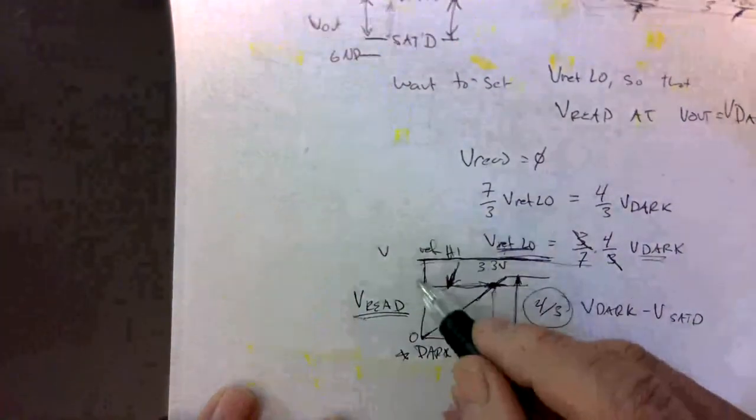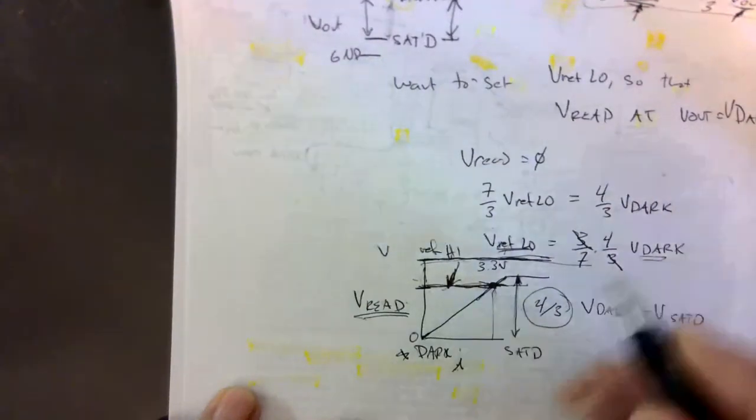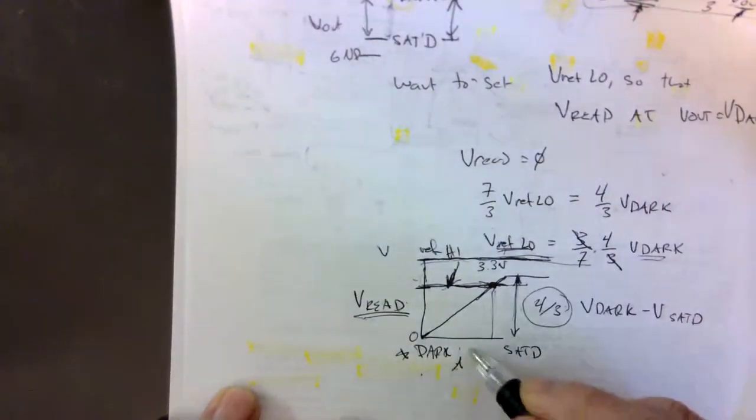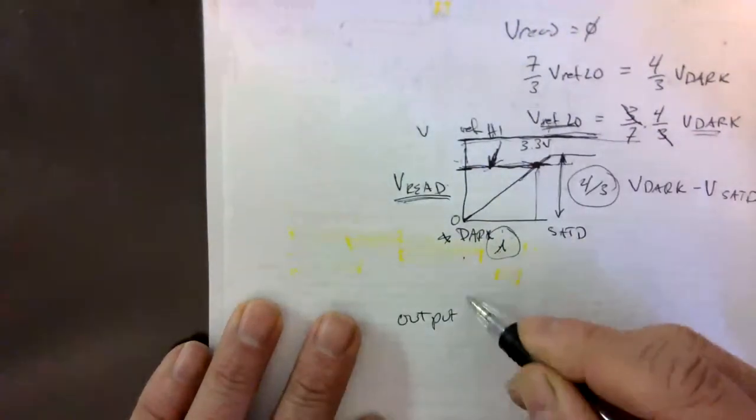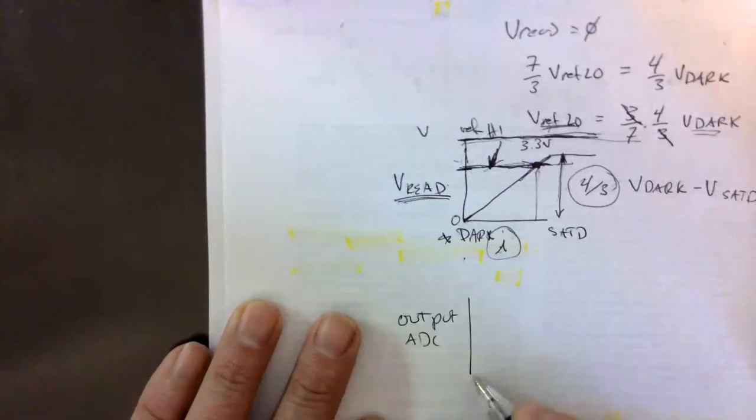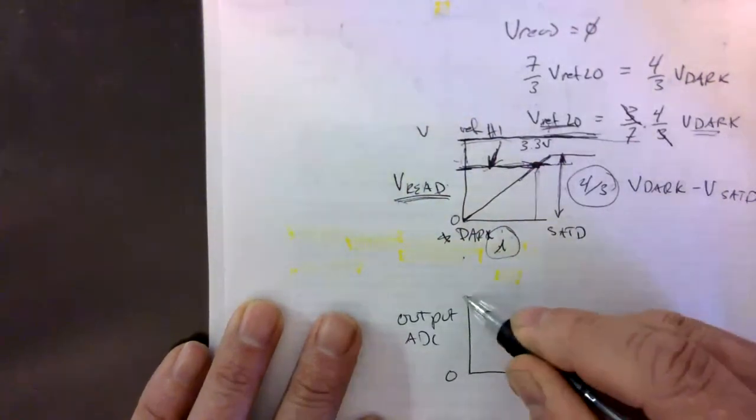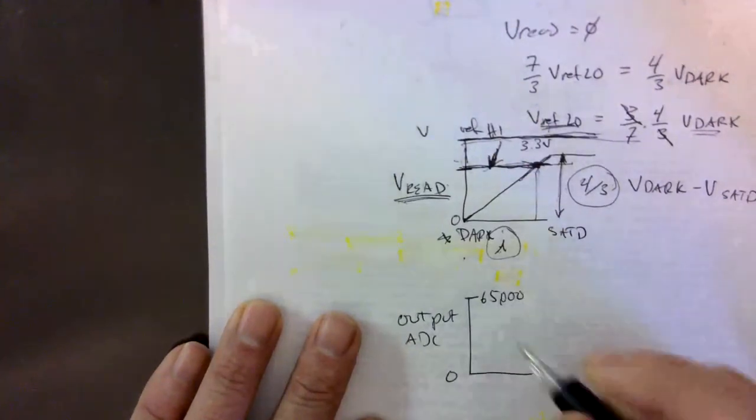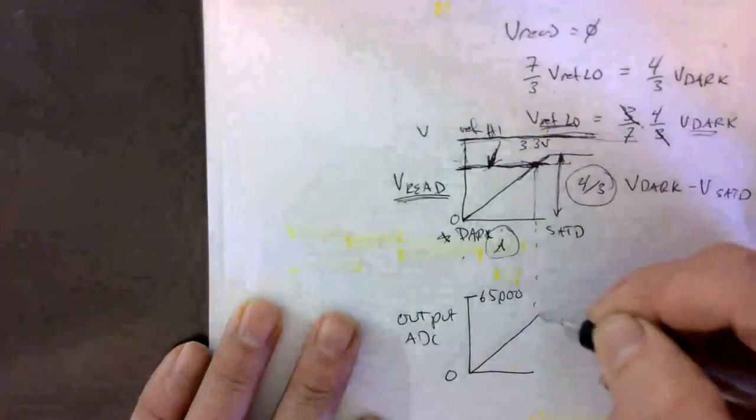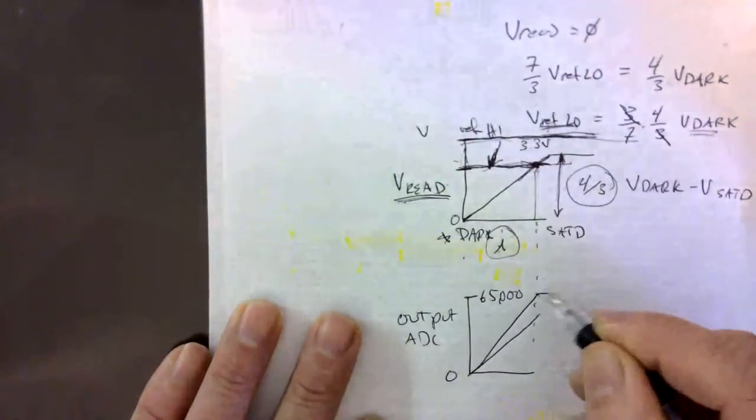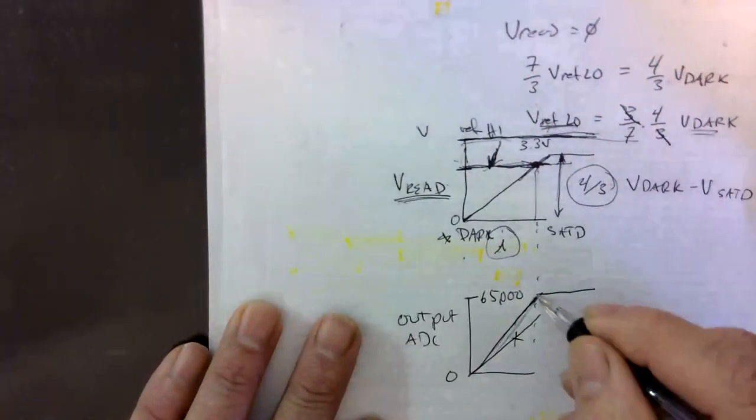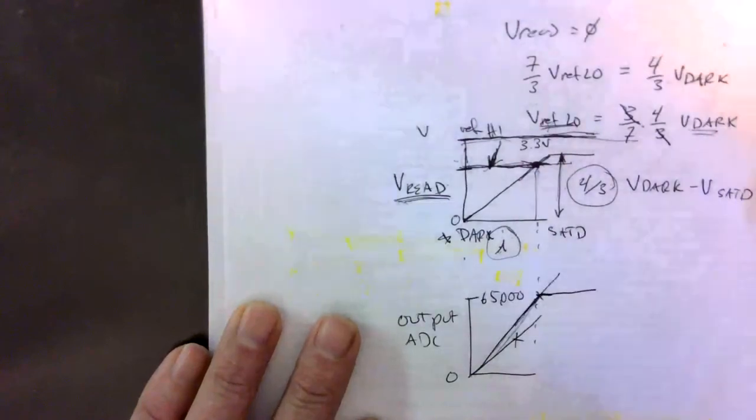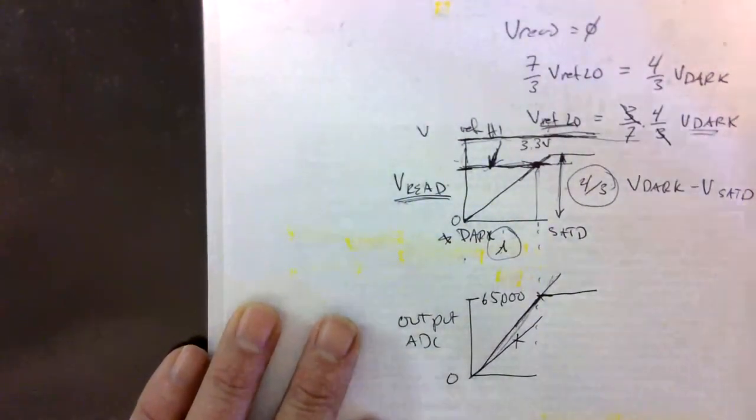So if we set our V ref high here, then we can measure intensity versus the output from our ADC. We will go from zero to about 65,000 at this point, and then it is flat. So we want to make sure that 65,000 is on the linear part of the output. That is all I am trying to get to.